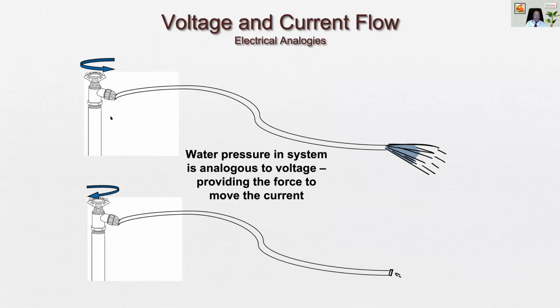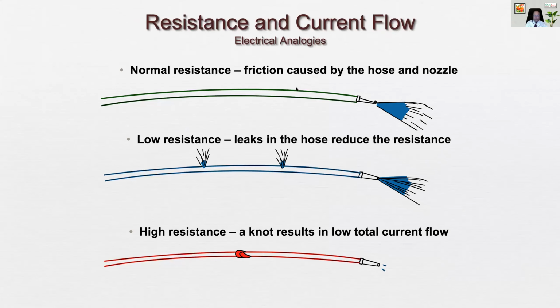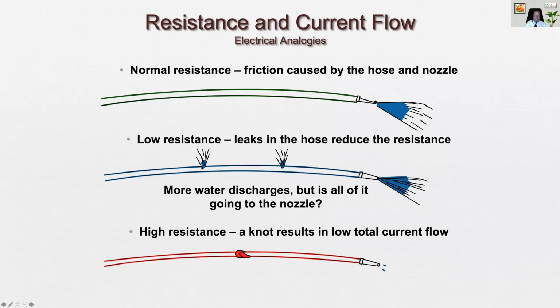Similarly, in the case of the leads, we can visualize the leads like water pipes. So with a normal, intact water pipe, there may be a certain flow of water. But if we open the tube from the side, there may be more leakage of water. So some flow may decrease to the tip. And of course, the wastage of water will be increased. So the same thing happens in the pacemaker system. If the insulation is broken on the lead, there may be leakage of current from the sides of the lead, which would go in the body, not produce any effect usually. Sometimes it may stimulate the muscle and cause twitching. So it may stimulate the pectoral muscles and cause twitching, but the flow may be maintained or decreased slightly, but the battery will drain very fast.